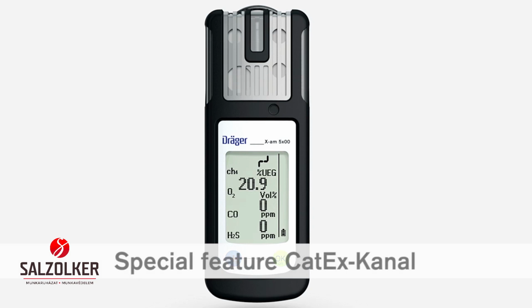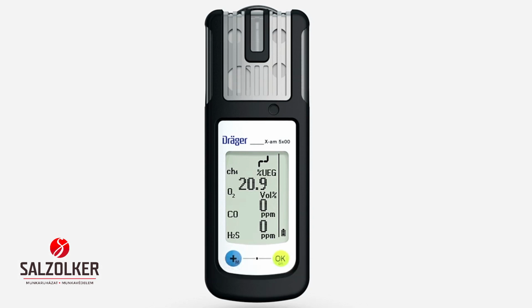There is a special feature in the Dräger X-am 5000 with CatEx sensor. A lock alarm is sounded if the measuring range is exceeded by a significant amount, meaning that very high concentrations of combustible substances are received by the CatEx channel. This CatEx lock alarm can be manually acknowledged by turning the device off and then on again in clean air. The lock alarm is displayed by this icon.